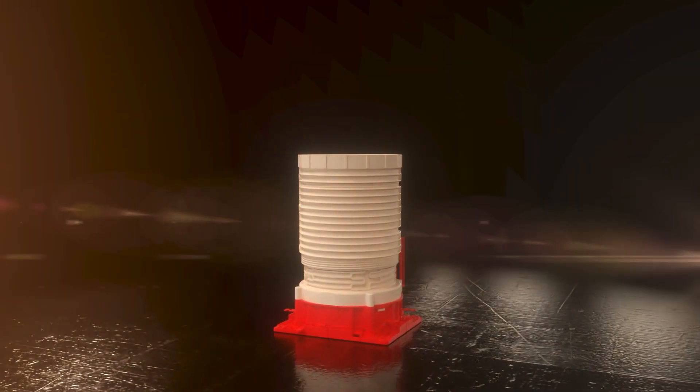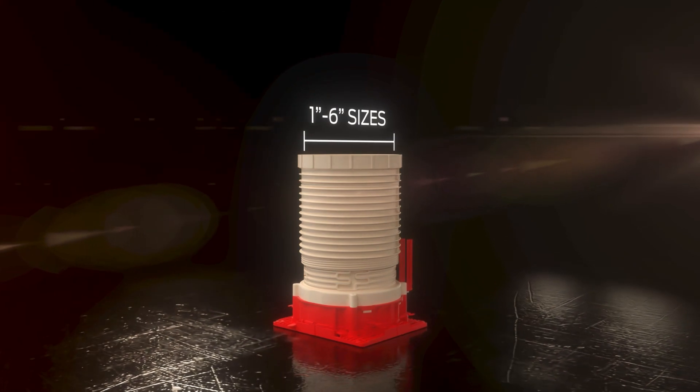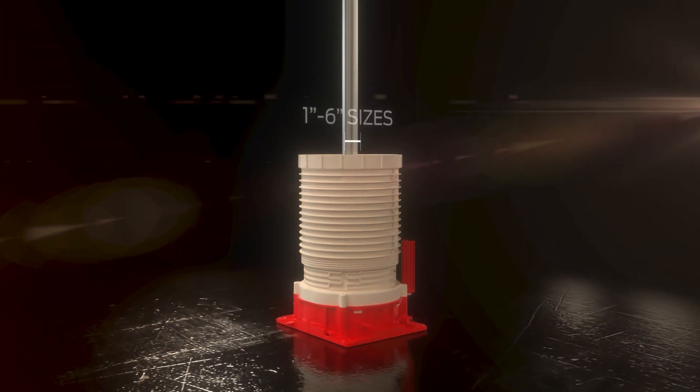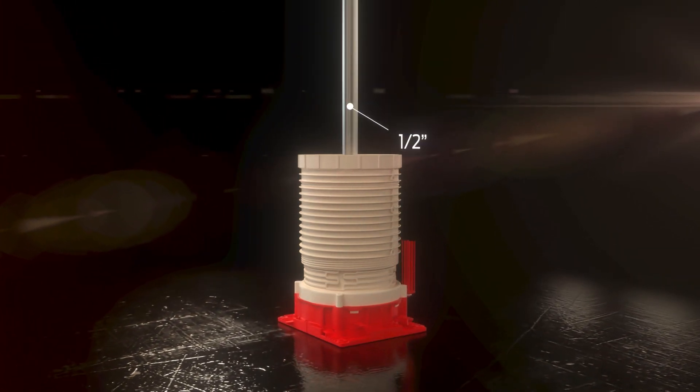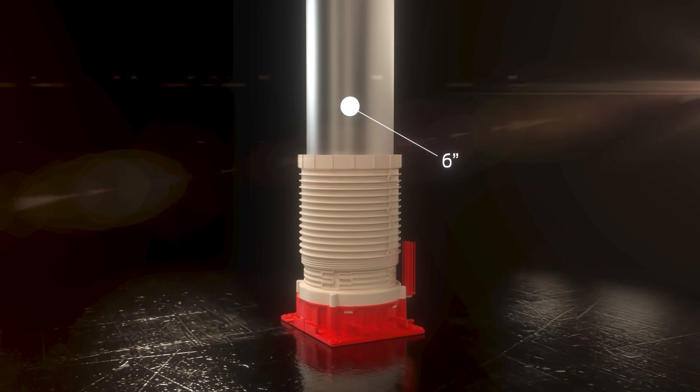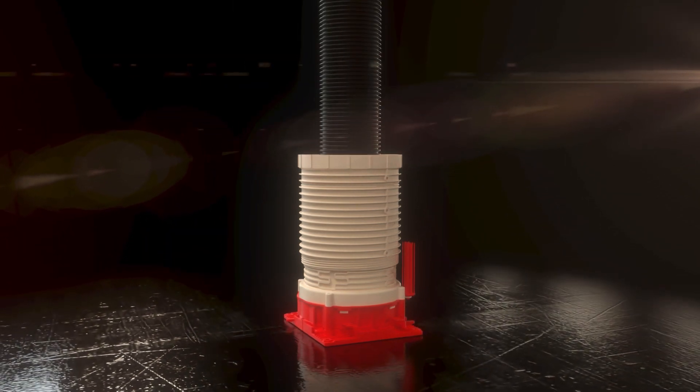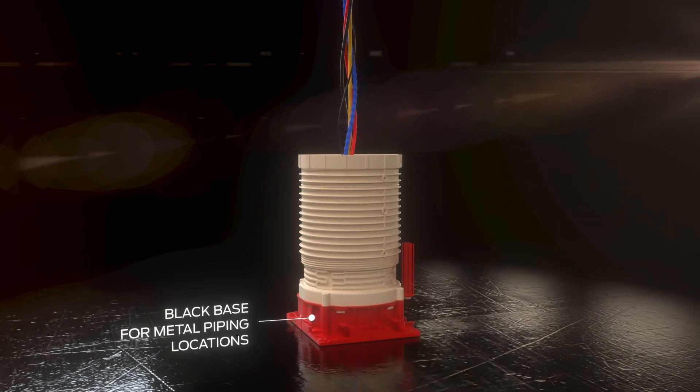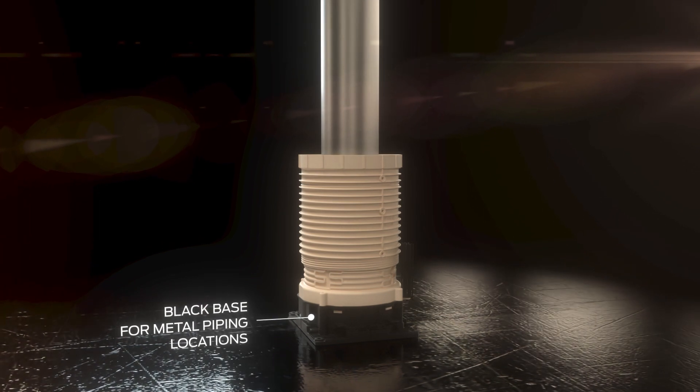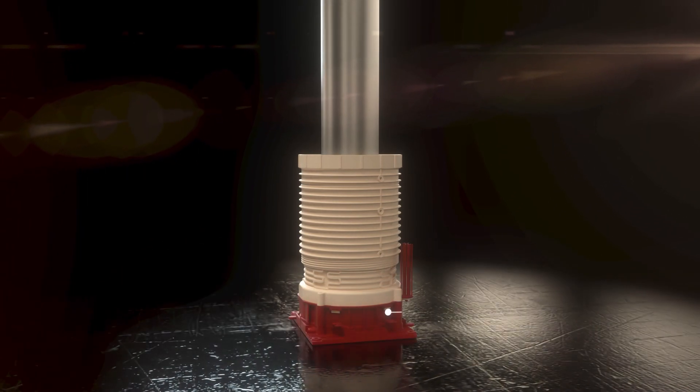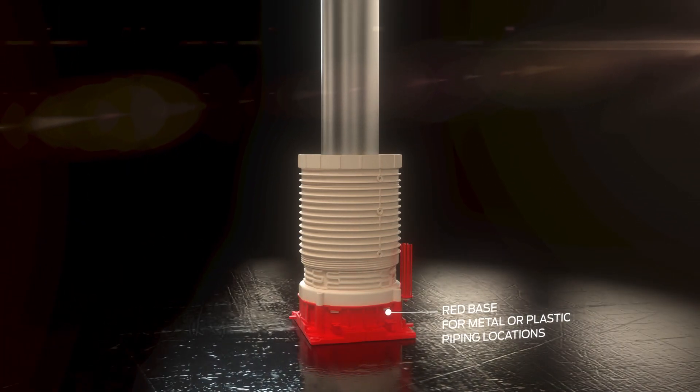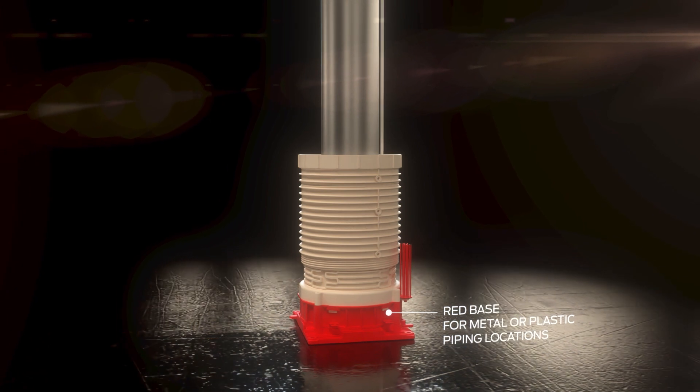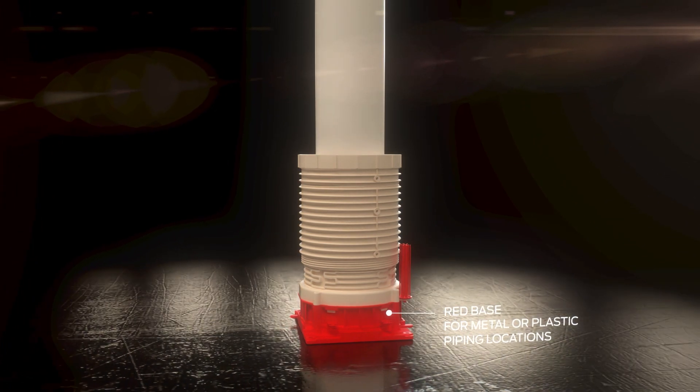The Hydro Flame Pro is available in 1-inch to 6-inch sizes to accommodate penetrants from 1-inch to 6-inch in size, including piping, conduit, cables, and more. The Black Base and Locator Whisker Option is for use with metal piping penetrations, and the Red Base Whisker Option is for use with either metal or plastic penetrants.